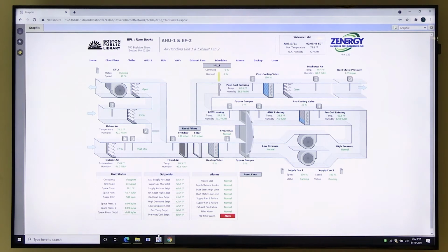How are they getting statuses from the fans? Is it CTs measuring current? Status from the fans is a relay contact on the drive. So all the drives are ABB. It's not reading actual work being done. It's actually just reading whether or not it's energized. Well, it's based on what the drive's determining is work. So as long as there is a current draw and it's actually doing something, I think that's when that relay is going to start, is actually going to make.